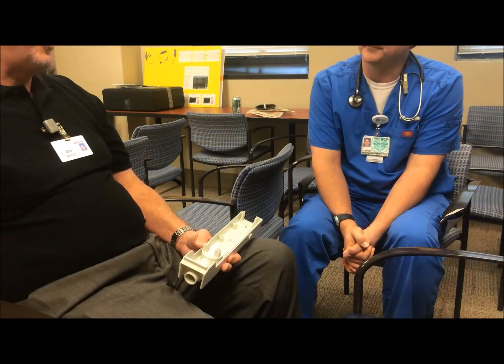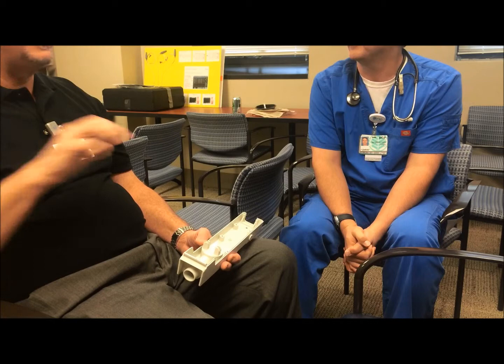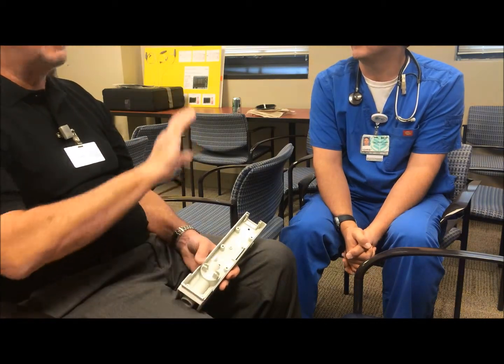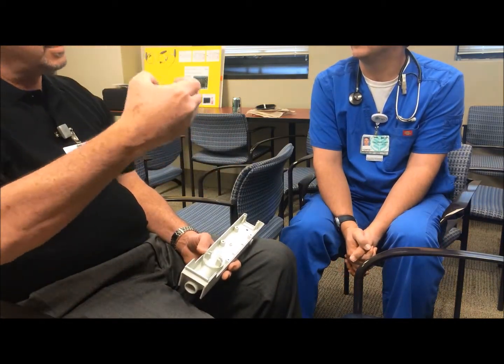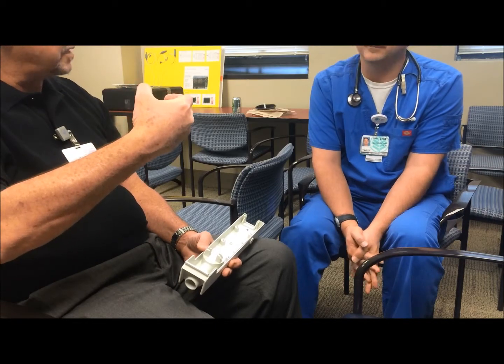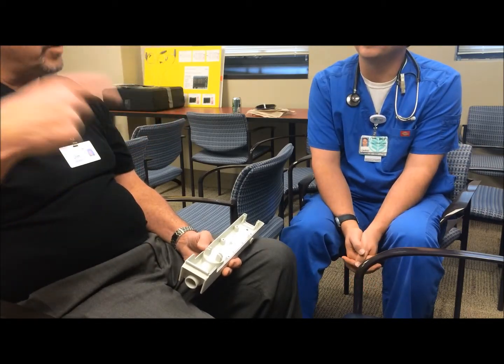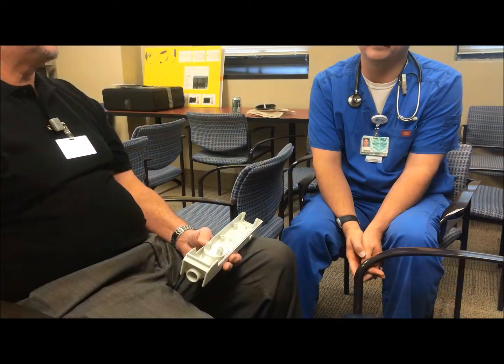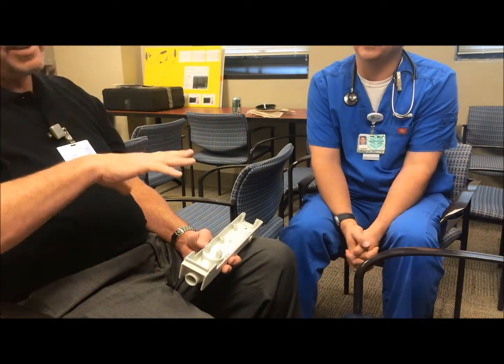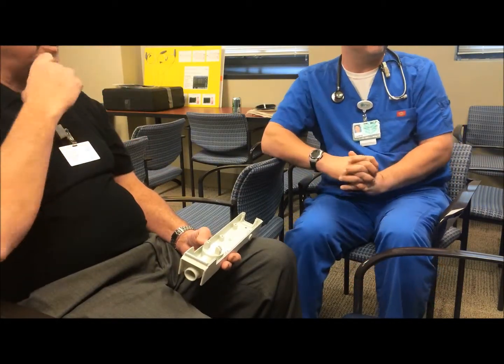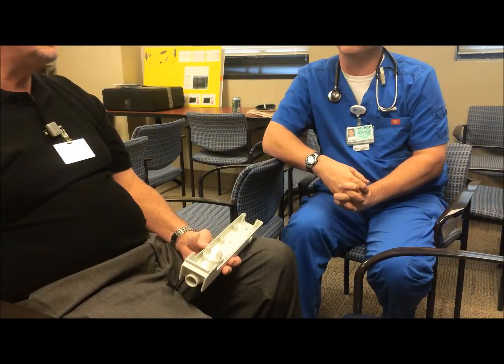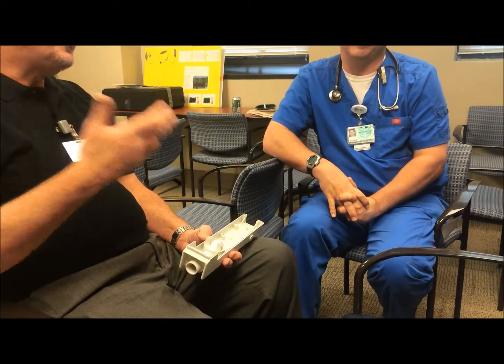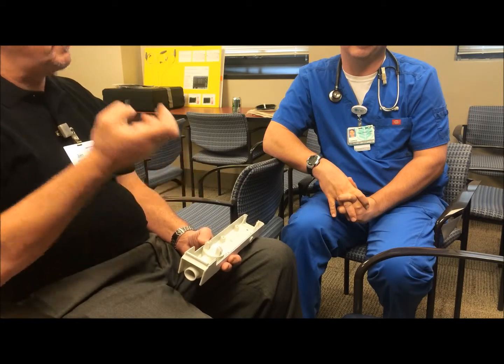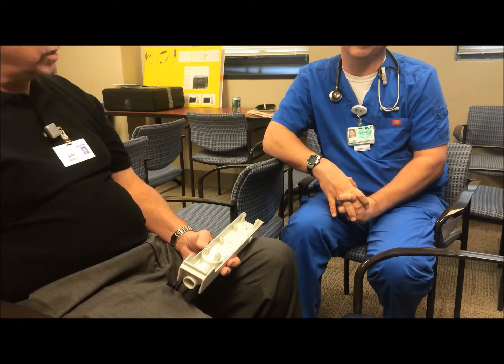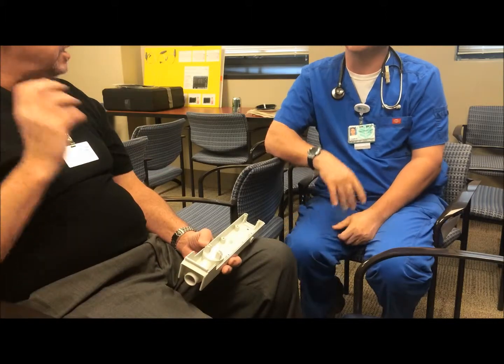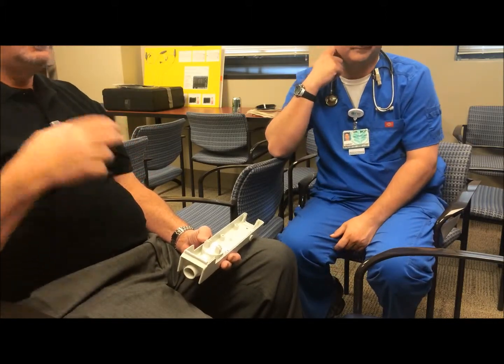As a matter of fact, when the ventilators first came out, before the Aerogens, I would say, don't buy the ultrasonic. It's not worth it, because the ultrasonic itself costs $350. You have to reuse them and clean them, and so they're going to get lost. So I'd say, don't really buy them. Don't add to the cost of the ventilator, because you're going to end up losing those things after a while. Or if you do get them, only use them on your worst asthmatic, the ones you need to deliver the very best treatment that you can to. But otherwise, don't get them.